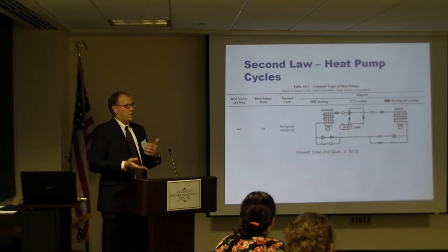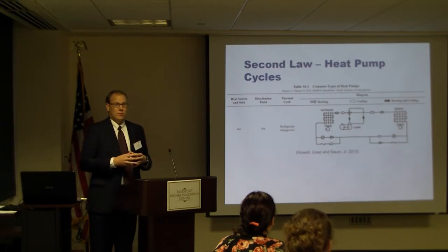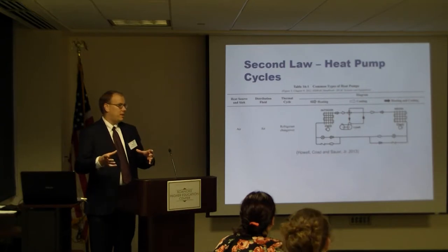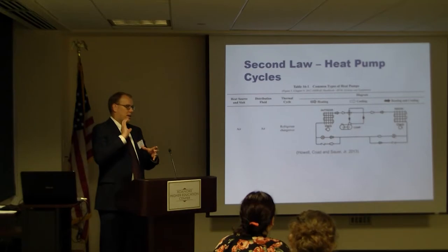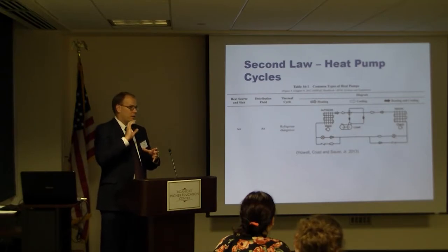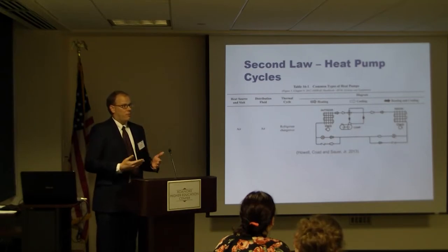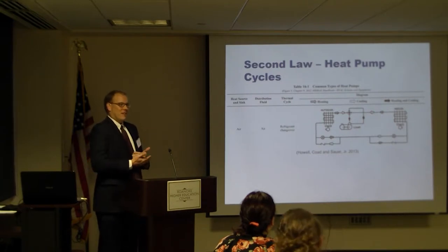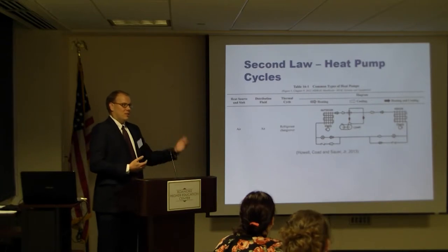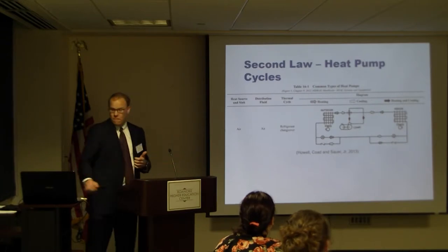We can manage that by oversizing the well field, so sometimes we have more capacity than we need in there, so we don't charge it all the way up in the summer. And we extract just a little bit more out in the winter, and we keep that cycle going. Eventually, the well field becomes oversaturated. That's one of the challenges we end up having with geothermal: not necessarily the day one design, but how we manage the year 20 design and beyond.